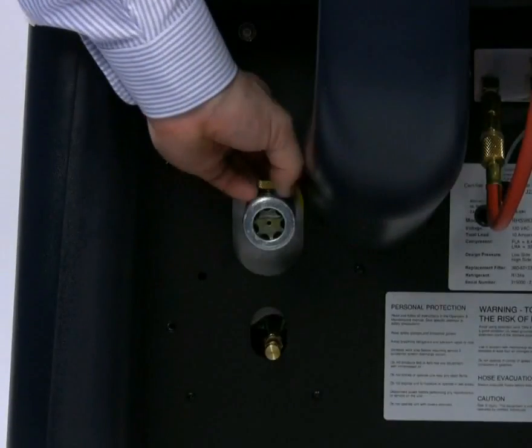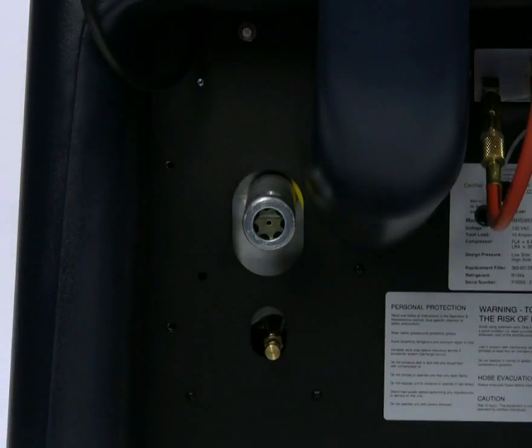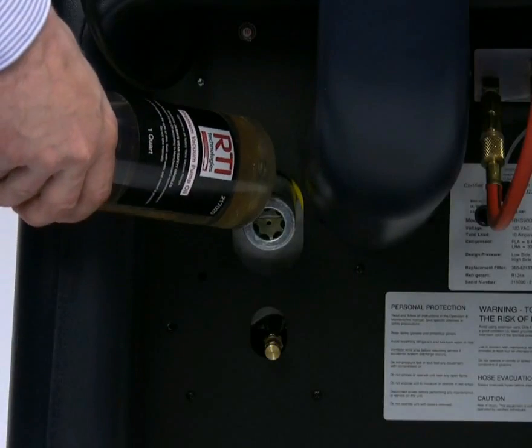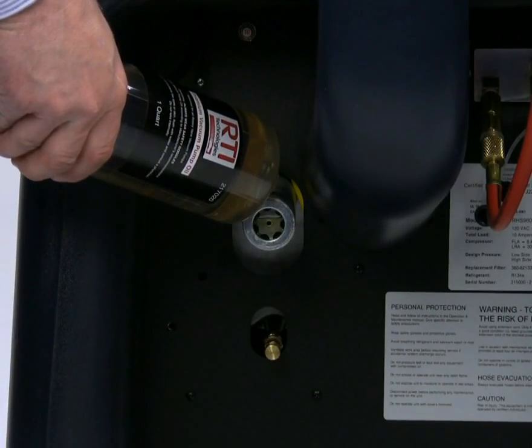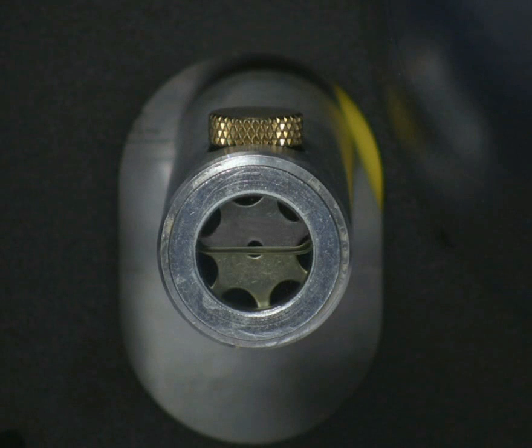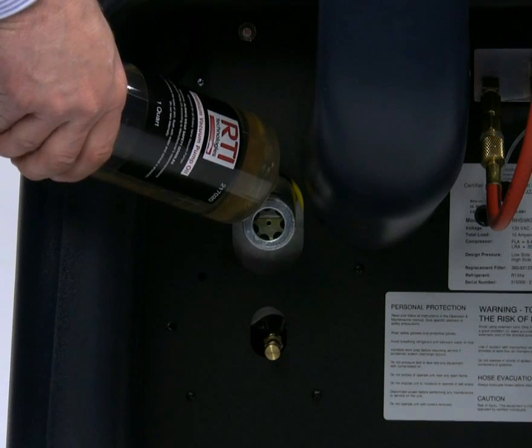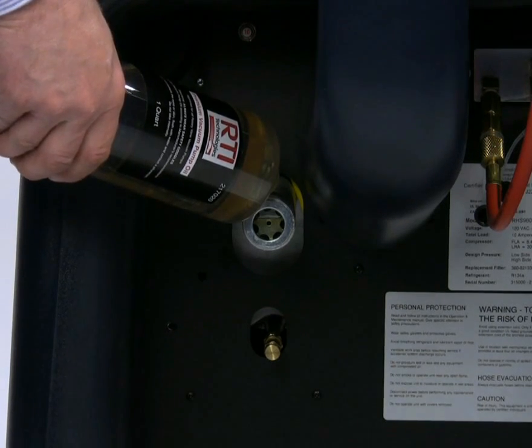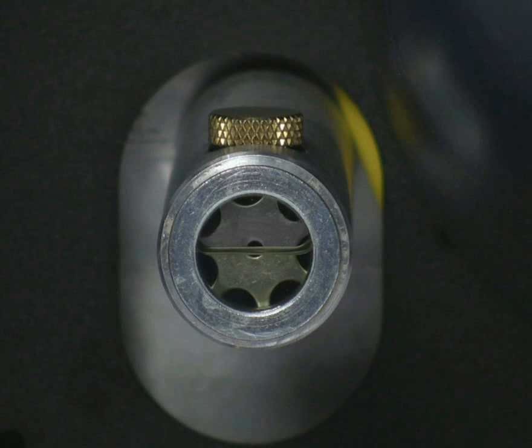To replace your vacuum pump oil, drain oil from the drain port and refill with new oil through the fill port as shown. Use only oil which is specifically formulated for RTI Technologies vacuum pumps. The sight glass on the end of the vacuum pump extension lets you see the new oil level in the pump. Fill until the level reaches dead center in the sight glass, being careful not to overfill. RTI recommends 5 ounces of oil for initial fill. Start the vacuum pump, then check the oil level. Keep adding oil until the level stabilizes dead center in the glass with the pump running.